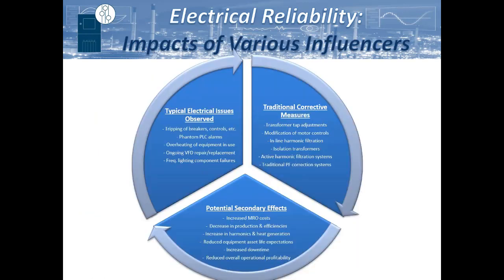So some of the things that are often seen out in the world, some typical electrical issues, are phantom tripping, whether that be of breakers or of motor controls or of soft starts. You're also going to have phantom PLC alarms where things will trip out and it's not really understood exactly what occurred, but you have to stop the process, restart it, and get it going again. With integration of more and more VFDs, oftentimes we're seeing more and more VFD repair and replacement costs. And secondary impacts, oftentimes not attributed to power quality, can be significantly impacted by the power quality on that network.